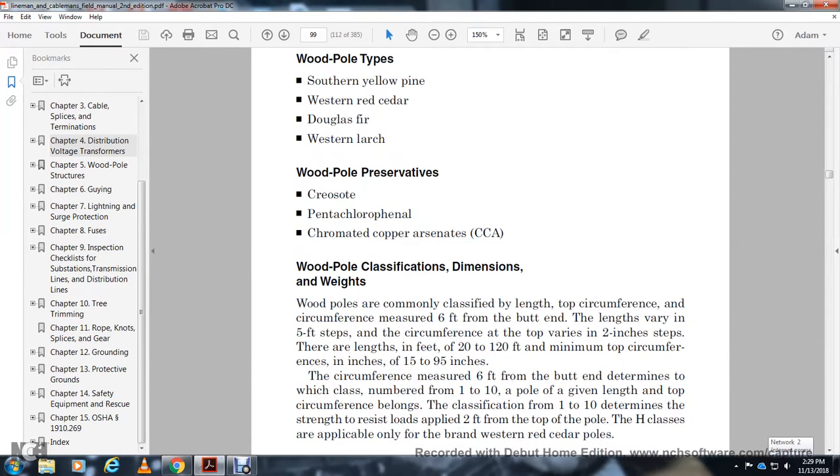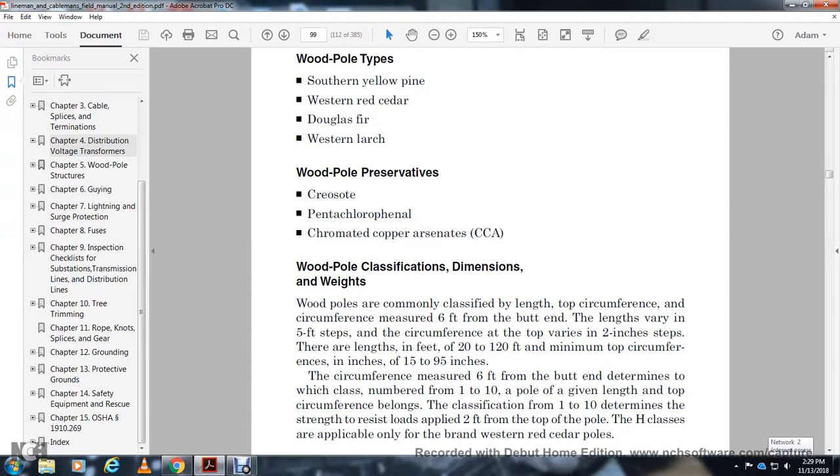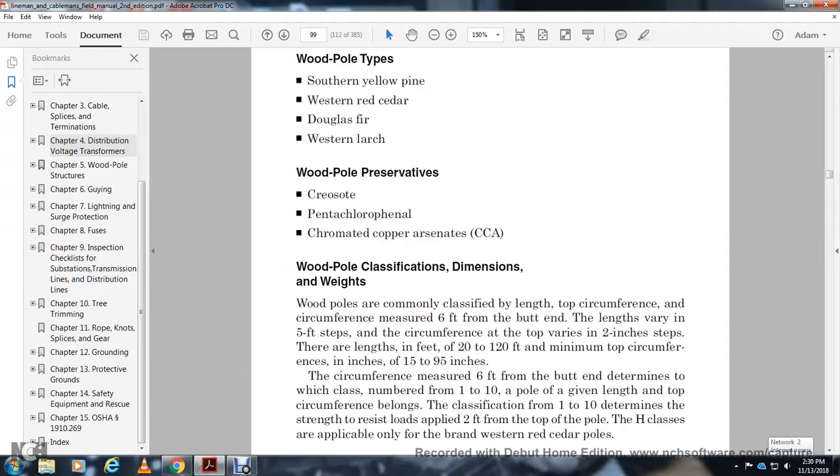Wood pole classification, dimensions, and weight. Wood poles are classified by length, top circumference, and circumference measured six feet from the butt. Lengths range from 20 to 120 feet with minimum top circumference of 15 inches. Circumference measured six feet from the butt determines the class, numbered 1 through 10. A pole's length, top circumference, and classification determine its strength to resist loads applied two feet from the top. Height classes are applicable only for southern yellow pine and western red cedar poles.